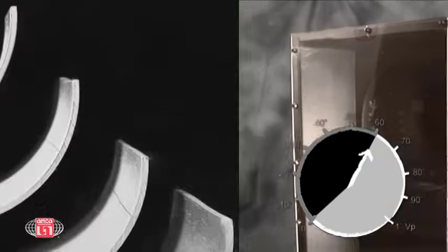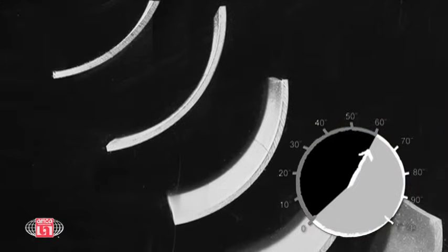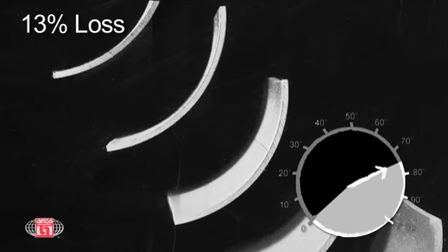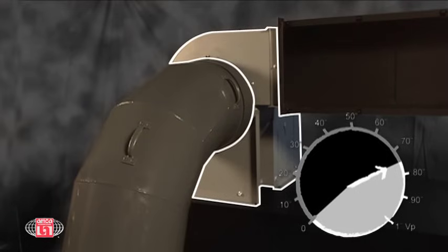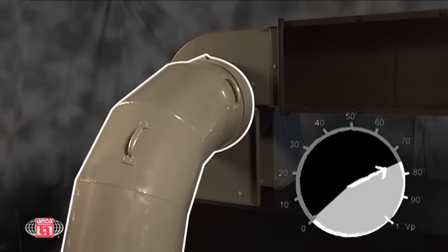If we improve the design by adding turning vanes to the inlet box, we improve the velocity pressure to 3 quarters of an inch water, but that's still a 13% loss of air flow. Changing the inlet box to an elbow will help. Properly installed, a sweeping radius elbow can result in only a 3% loss of air flow.